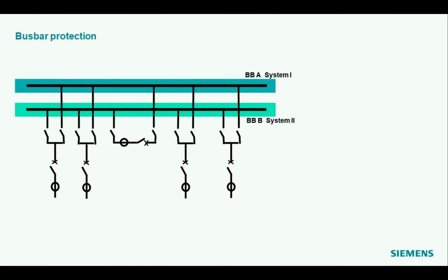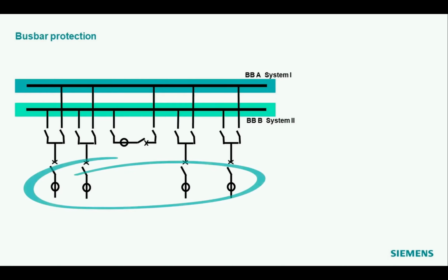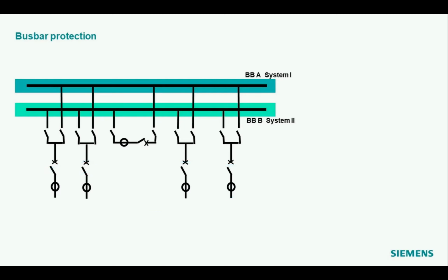For that reason, I would like to show this example with a double busbar substation. You see here 4 outgoing feeders, double busbar, and every feeder has 1 circuit breaker, 1 current transformer, and every feeder can either be connected to busbar A or to busbar B, depending on the position of these isolators.